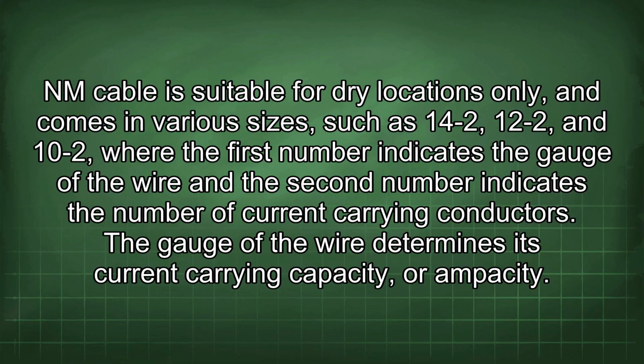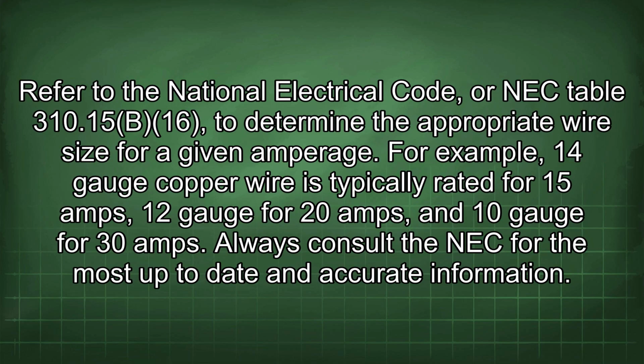The gauge of the wire determines its current carrying capacity, or ampacity. Refer to the National Electrical Code, or NEC Table 310.15(B)(16), to determine the appropriate wire size for a given amperage. For example, 14-gauge copper wire is typically rated for 15 amps, 12-gauge for 20 amps, and 10-gauge for 30 amps. Always consult the NEC for the most up-to-date and accurate information.